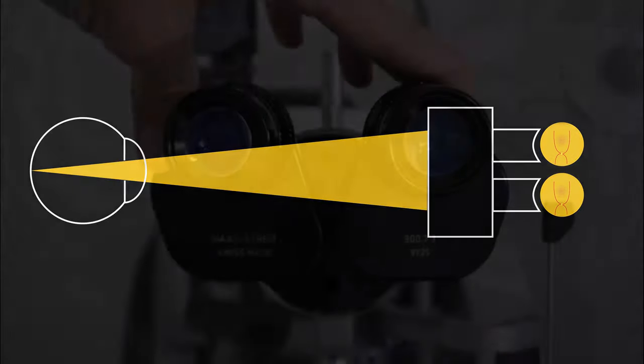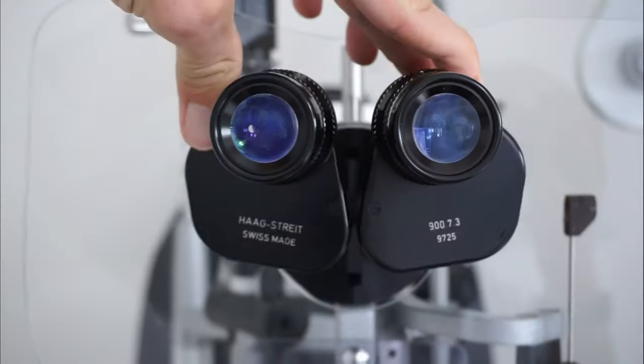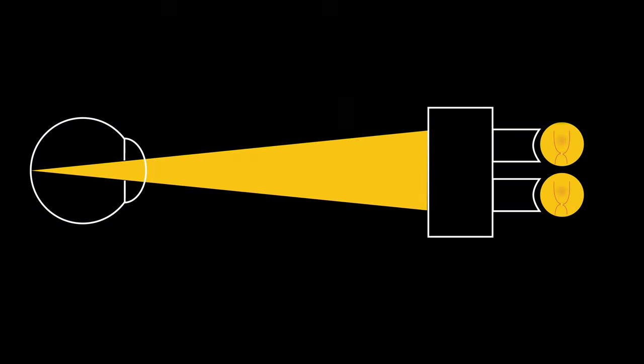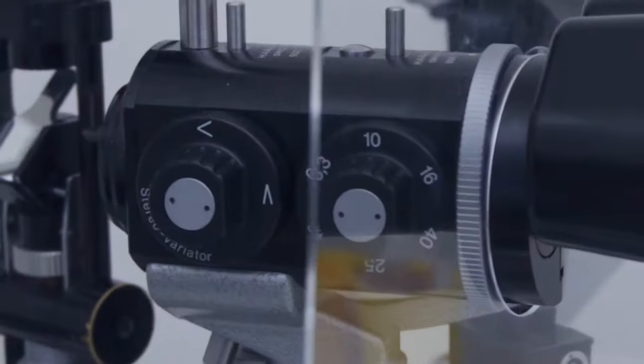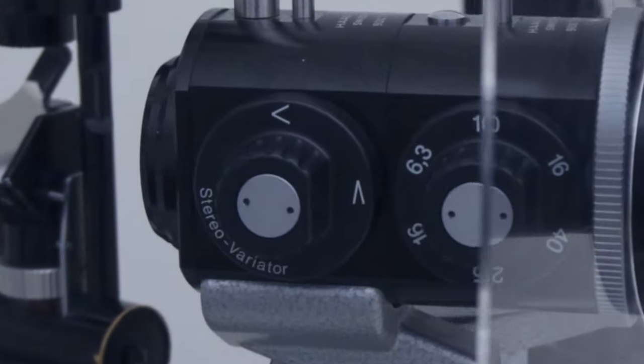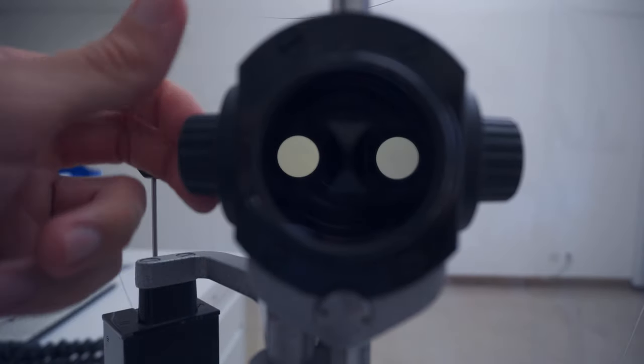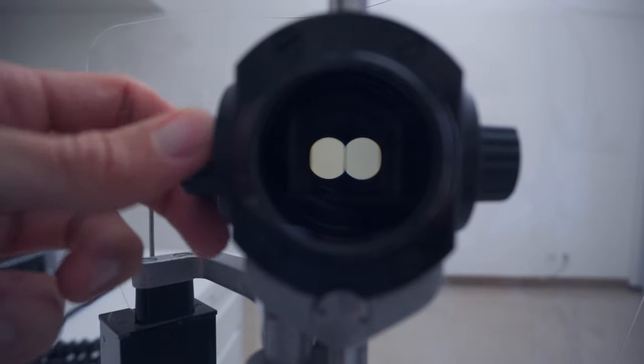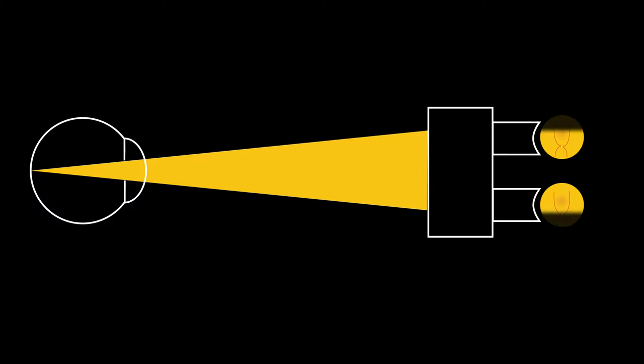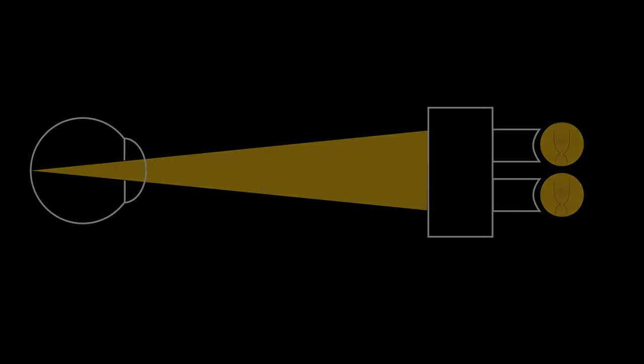And you know, just pushing the eyepieces closer together doesn't work. Of course the solution is the stereo variator. When you're setting your stereo variator to narrow, you're actually bringing your eyes closer together. And this then allows you to see an undilated patient's retina with both your eyes.